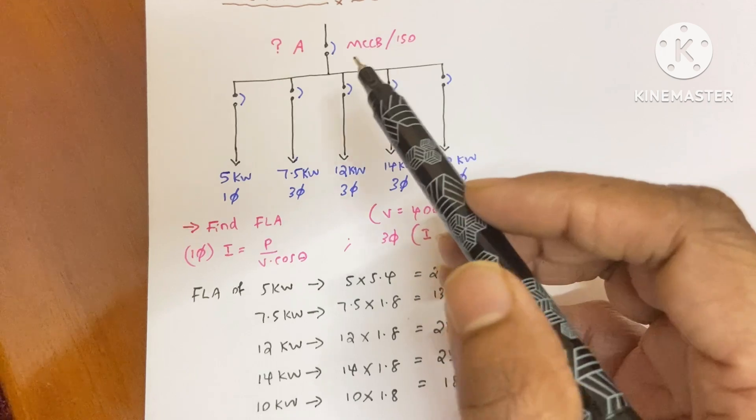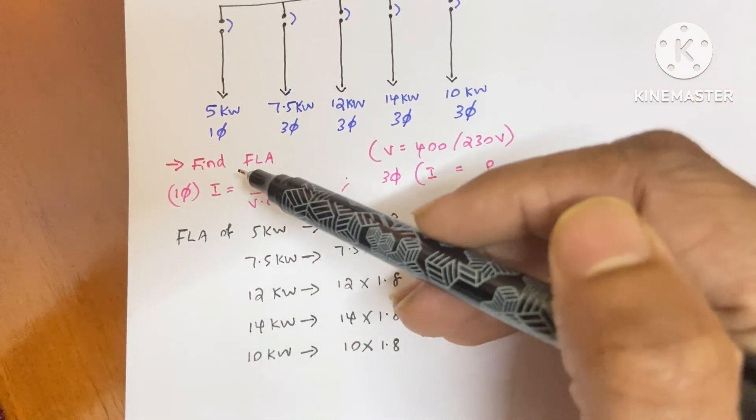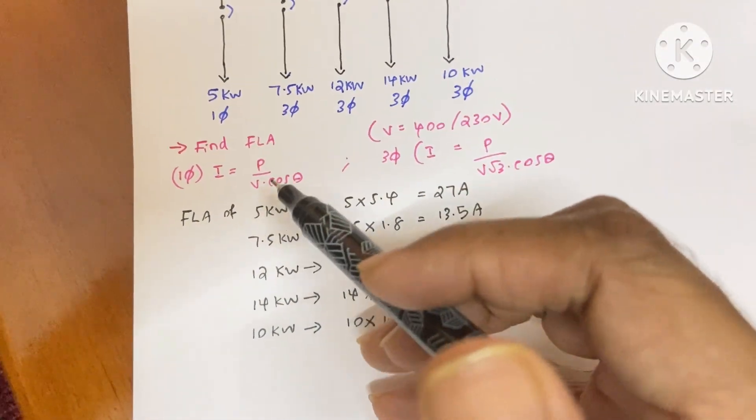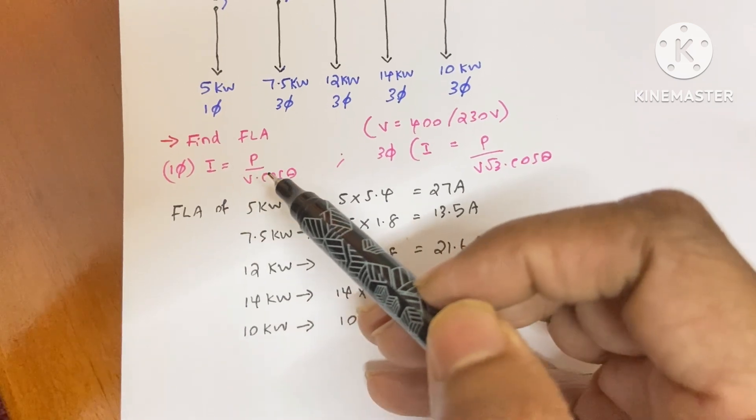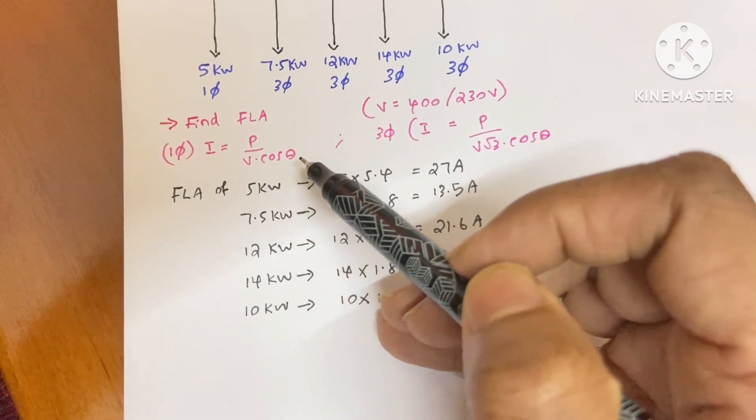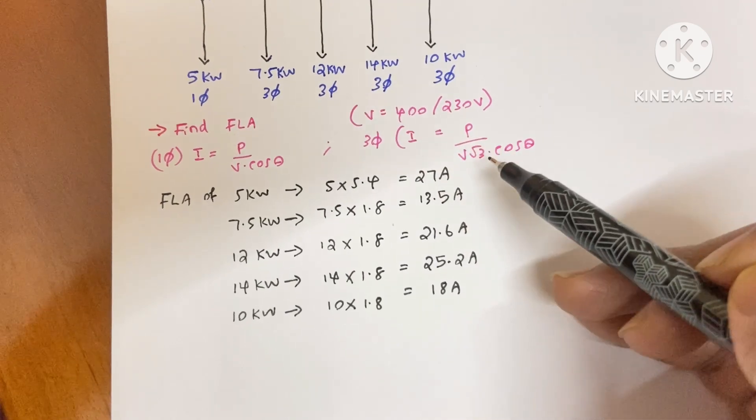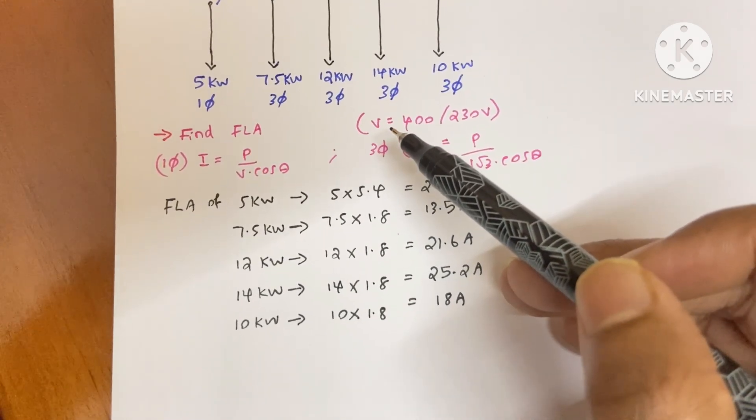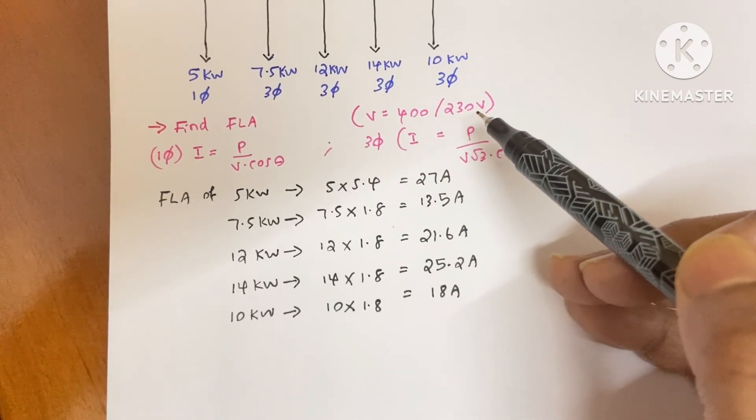To find the incoming breaker size, first we need to find the full load ampere of all these motors. For single phase, the equation is I equals P by V into cos theta. And for three phase, I equals P by V root 3 into cos theta. Here our voltage for three phase is 400 and for single phase is 230 volt.